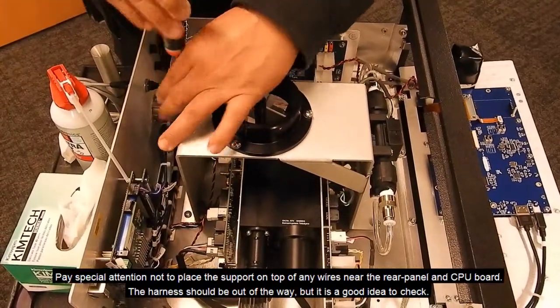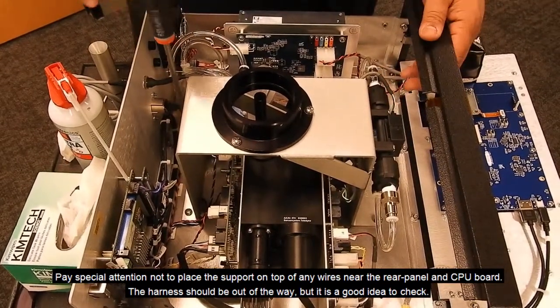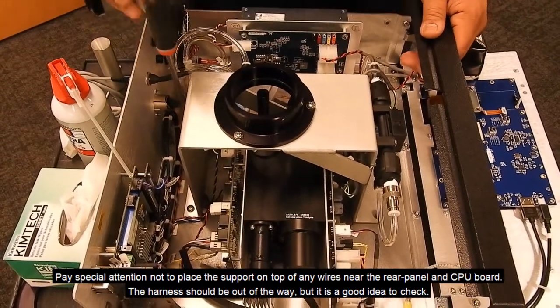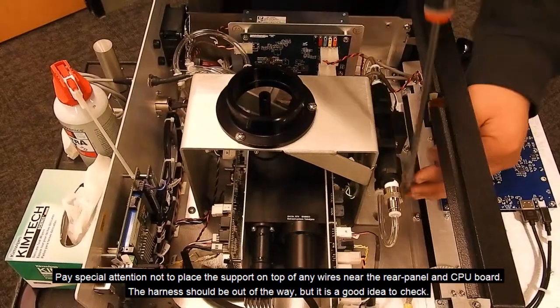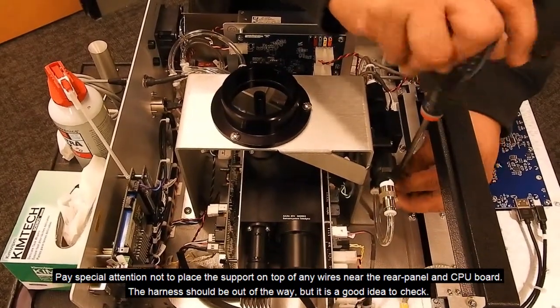Pay special attention not to place the support on top of any wires near the rear panel and CPU board. The harness should be out of the way, but it is a good idea to check.